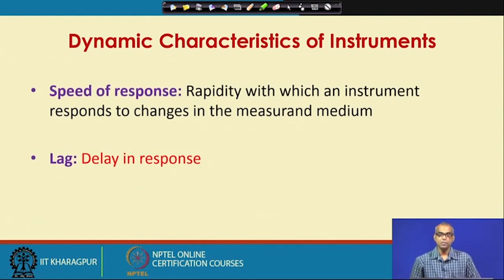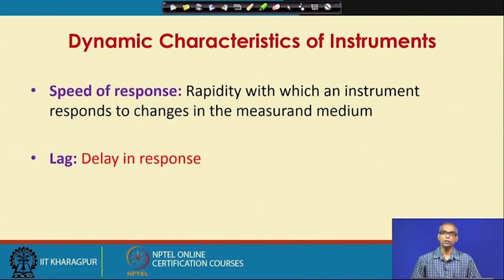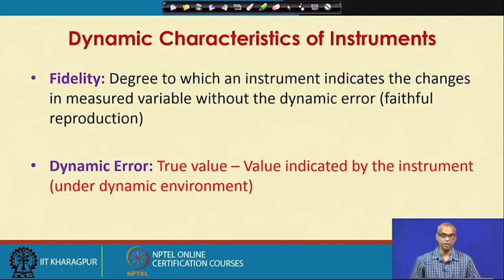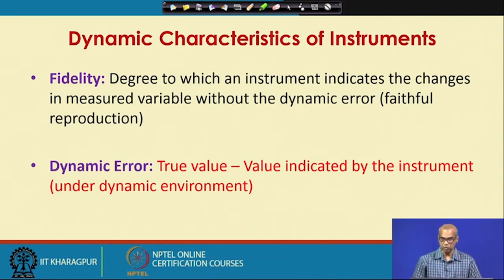Speed of response is defined as the rapidity with which an instrument responds to changes in the measured medium. Lag is the opposite — it is a delay in response. Fidelity is the degree to which an instrument indicates changes in the measured variable without dynamic error, meaning it is a measure of faithful reproduction. Dynamic error is defined as the difference between the true value and the value indicated by the instrument under dynamic conditions.